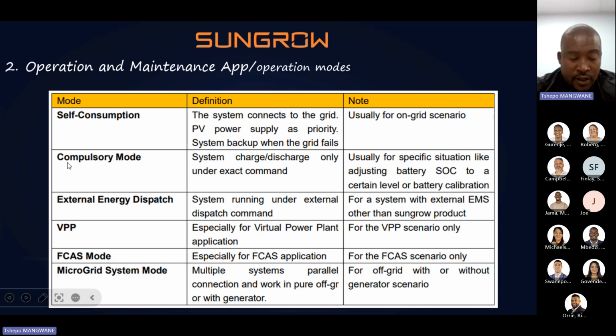Then let's look at compulsory mode. We mainly use it where it's only the inverter and battery. It's like a UPS system. The system will charge from the grid, but then discharge whenever the power is needed, maybe when the grid is load shedding or there is a power cutoff. There are no panels in this scenario, and we can set the system to charge or discharge by commands as well. Let's hear what Sungrow says. Compulsory mode definition: system charges or discharges only under exact command. The note says it is usually for specific situations like adjusting the battery SOC to a certain level, for battery calibration.